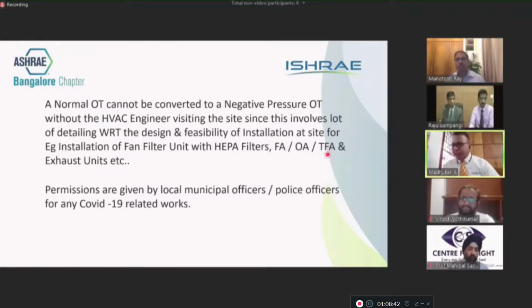Or the simplest thing we can do is have something called treated fresh air or treated outdoor air - air coming in at 45 or 35 degrees centigrade from outside can be treated externally to about 29 or 27 degrees centigrade, and then brought into your operation theater, without impacting the load on the air conditioning system within your air conditioned zone.